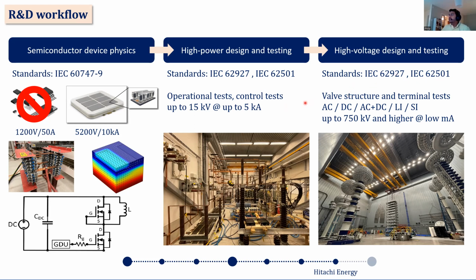Again, with the same two standards, we have different kinds of tests. We have AC tests, pure AC, pure DC. We have AC superimposed on DC because in HVDC converters, we have DC on one side, AC on the other, and this can cause different sorts of voltages in the valve. We also have lightning impulse and switching impulse, very similar to how we do it in cables. And this can go up to very high voltages, obviously with low currents, but extremely high voltages. And this is one of our high voltage labs. I'm not sure how many we have in total, maybe 4 to 5.